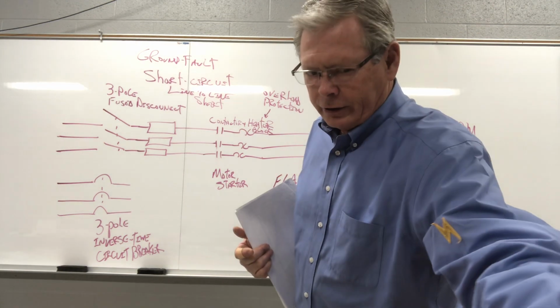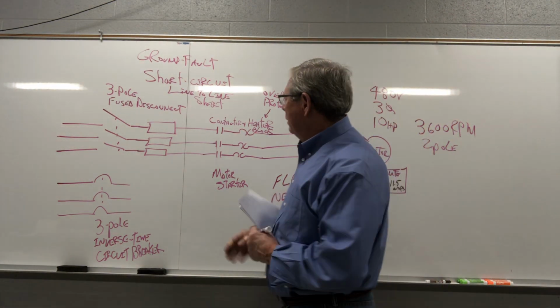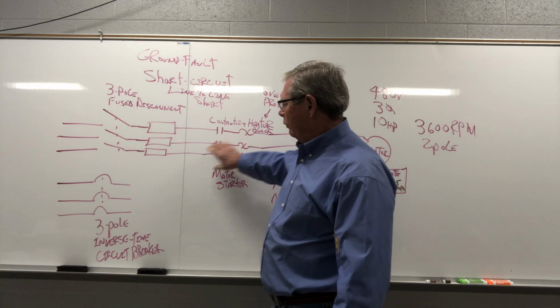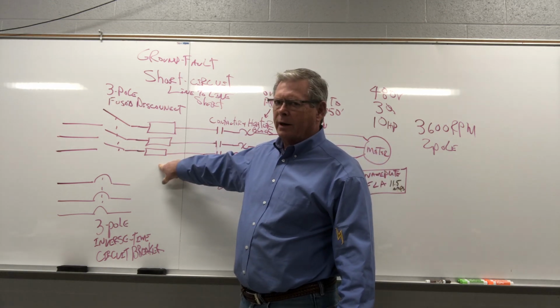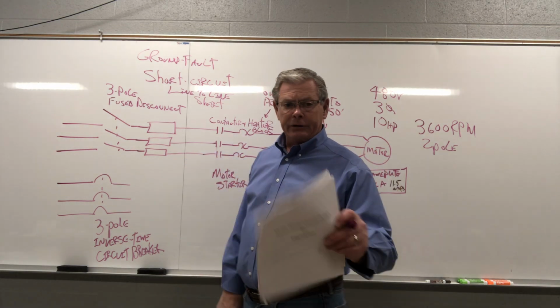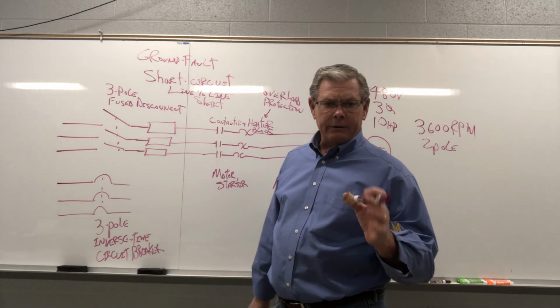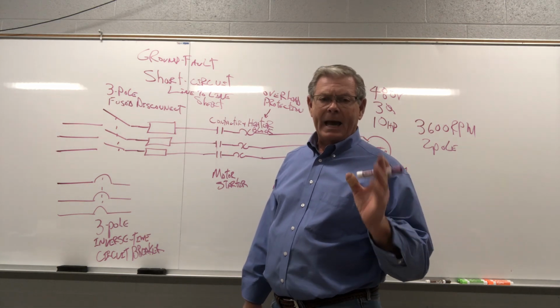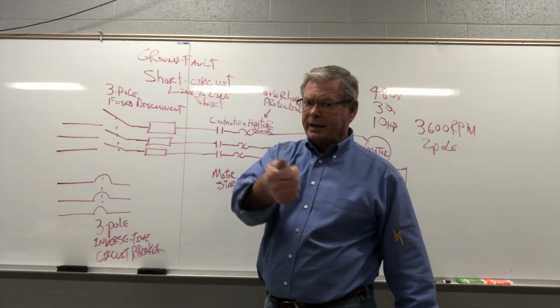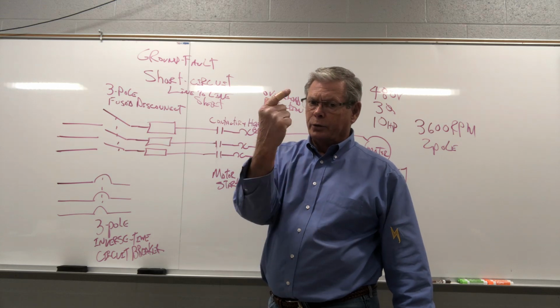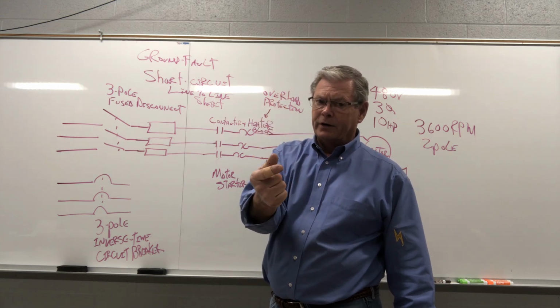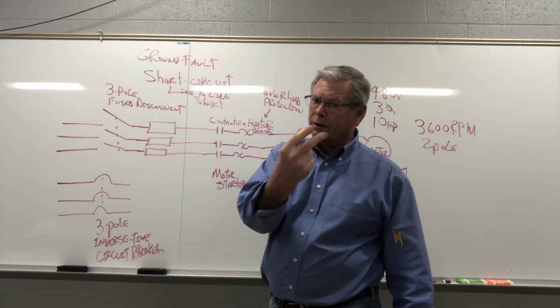In motor circuits, we separate overload from line-to-line short and ground fault. In your home, your breaker that feeds your living room has to do all three. It has to protect you from line to neutral short, has to protect you from a ground fault, and has to protect you from overload.